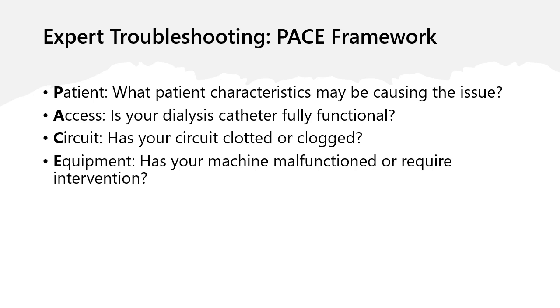Next, we have circuit. So this is where we consider some issues with the circuit itself. It could be that the circuit has clotted or clogged, and we'll talk about the difference here in a second. It could also be that some part of the circuit is not loaded onto the set properly if it's an alarm that has happened after the set has been primed and the patient's been on therapy. For example, it's not at all uncommon for the machine to get moved and for one of the pressure pods to get dislodged slightly and read pressures that are essentially impossible, and usually the machine is intelligent enough to figure out that a pressure pod has been dislocated.